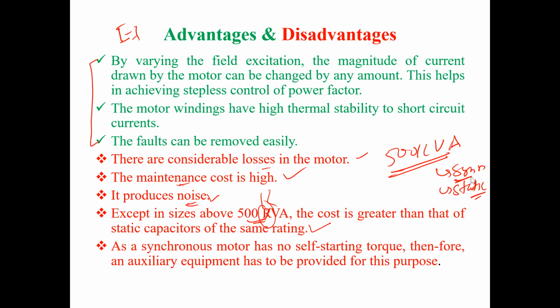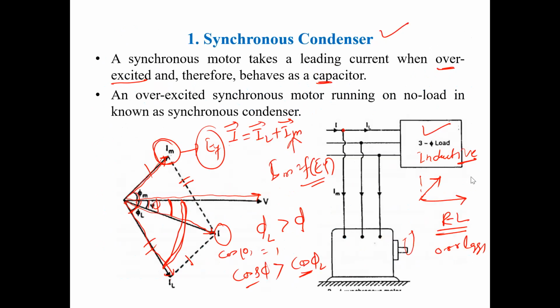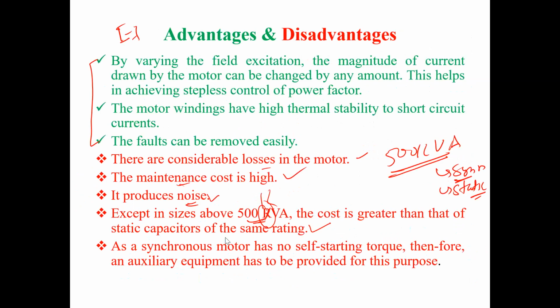As the synchronous motor has no self-starting torque, therefore, auxiliary equipment has to be provided for this purpose. That means our main motive here is to improve the power factor, but to start this synchronous motor we have to add an auxiliary starting system. Otherwise, our objective is only to improve the power factor. That means this system requires large maintenance and more auxiliaries for power factor improvement instead of a static capacitor arrangement.